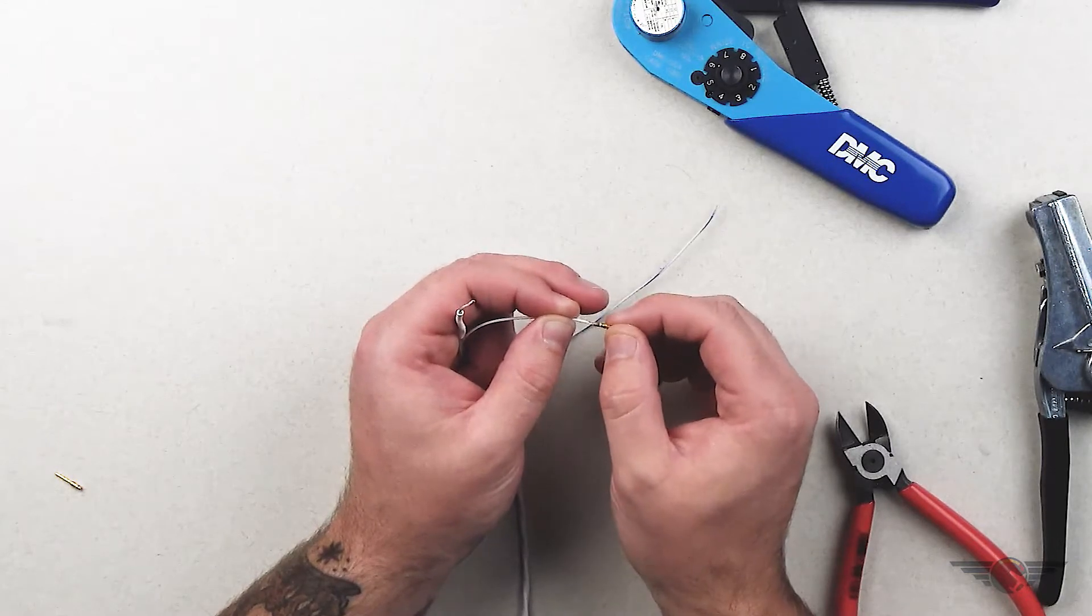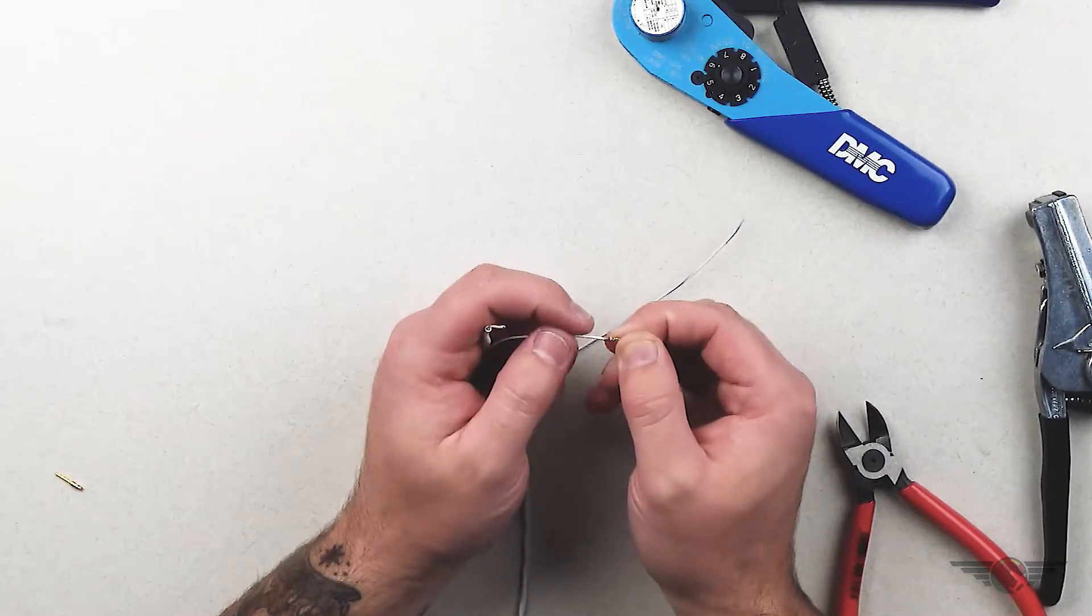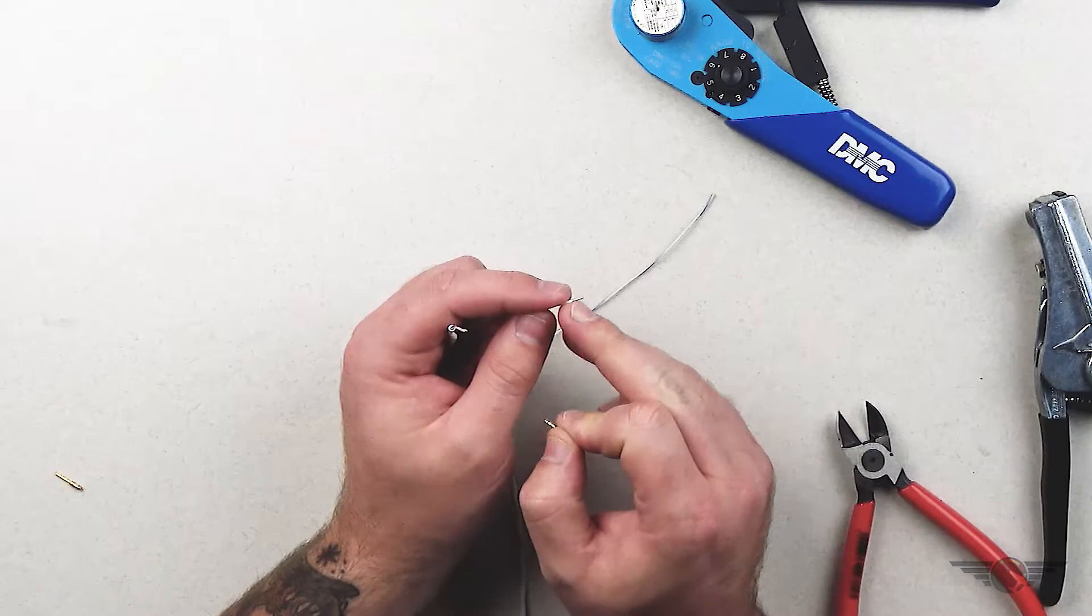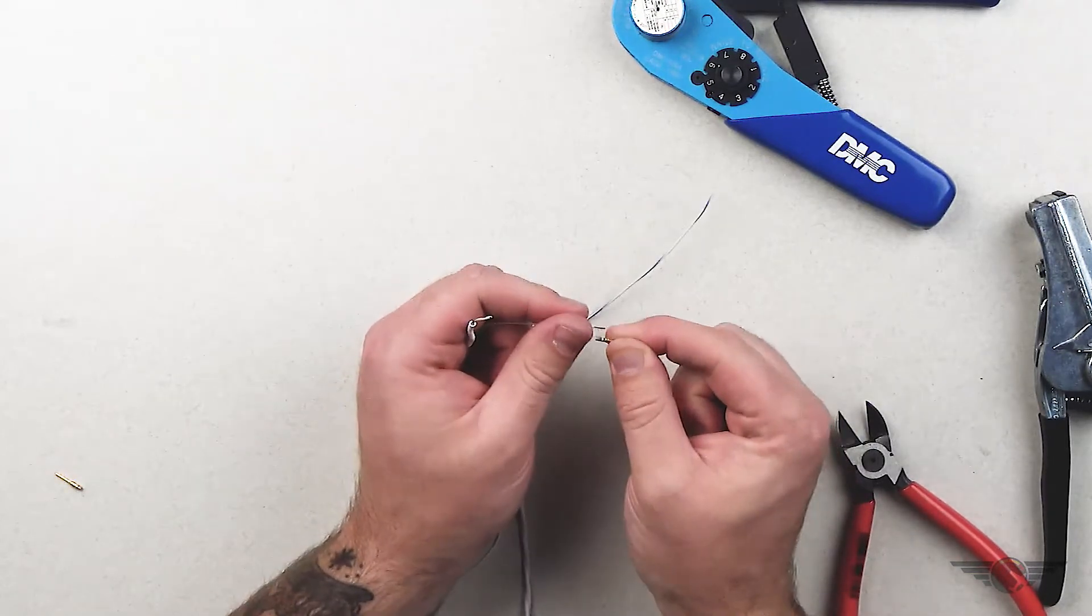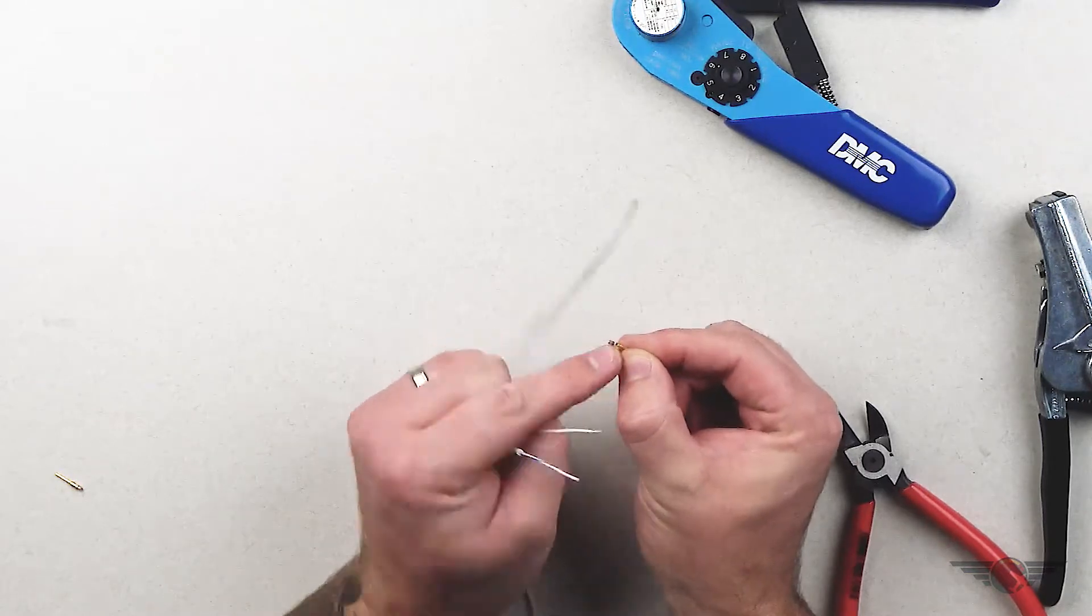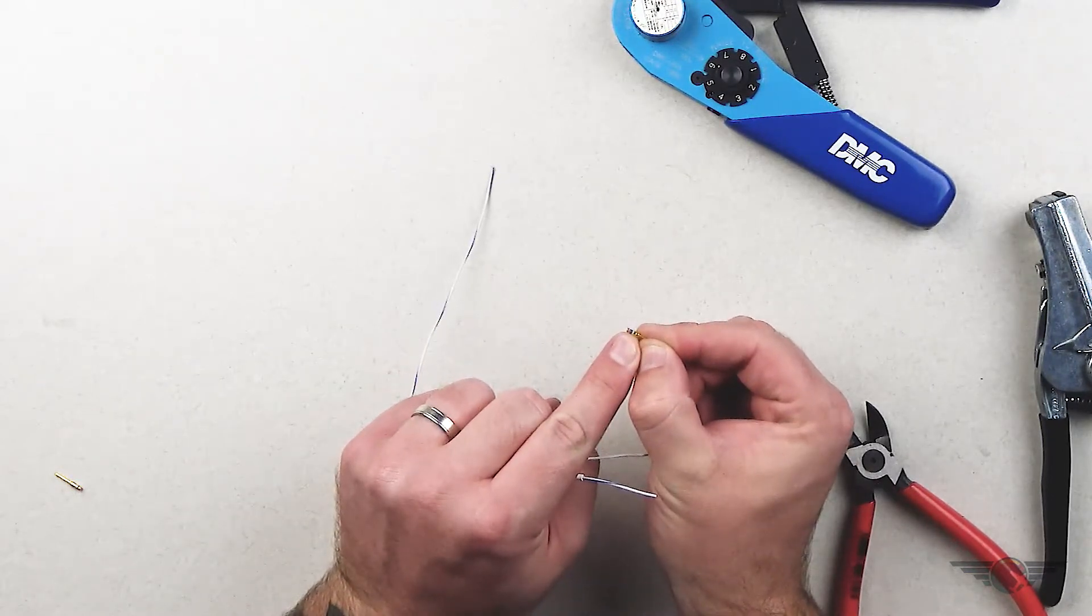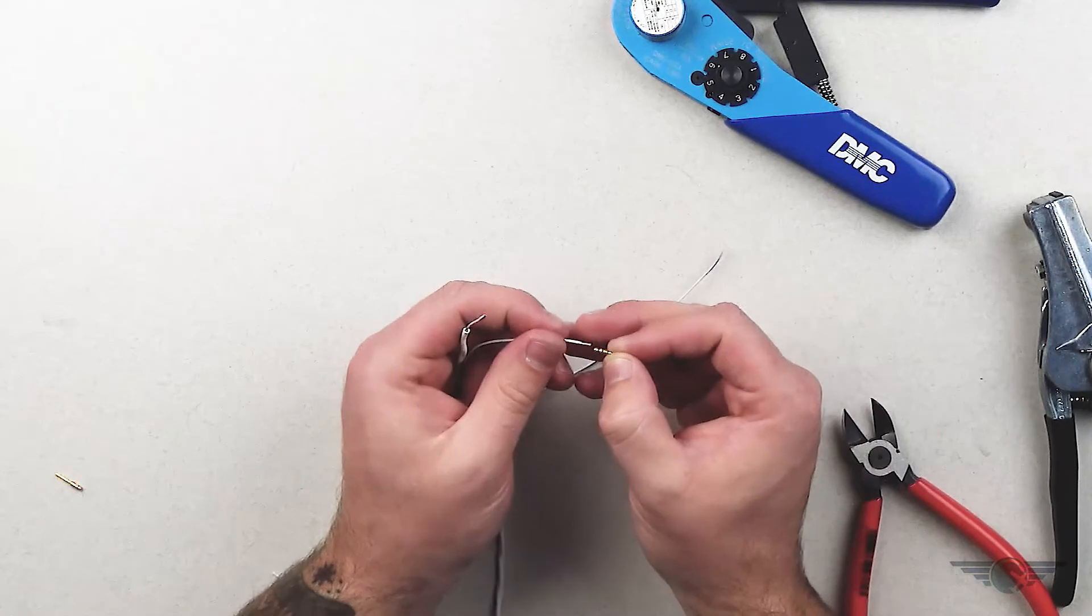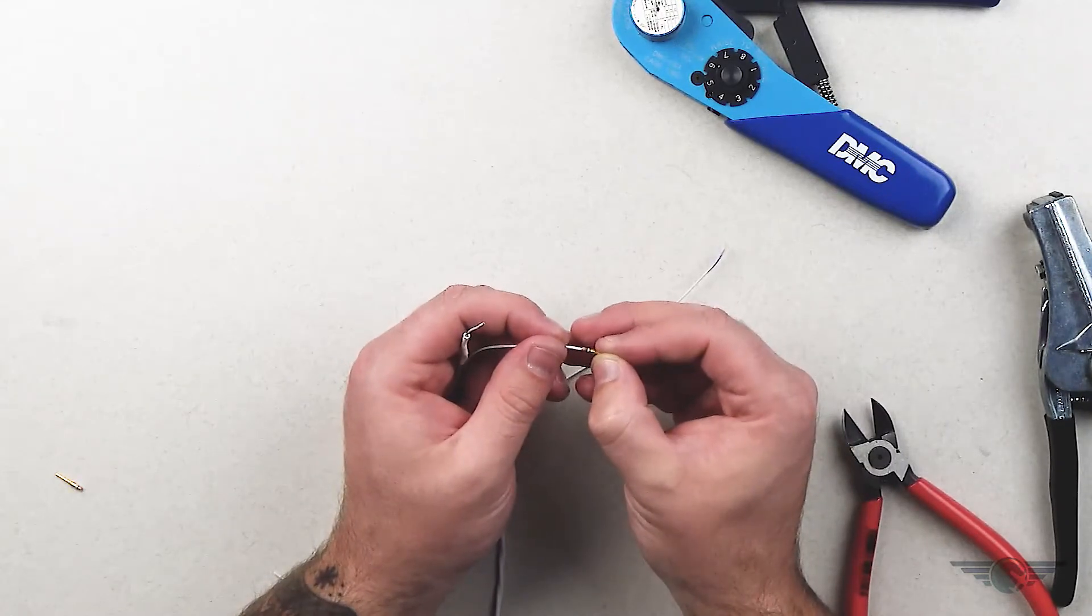Now what's important is you need a little bit of space between your insulation and the bottom of your pin. You also need to make sure you can see the wire in this window. There's a small hole in the pin—you need to visually see your wire in that window.